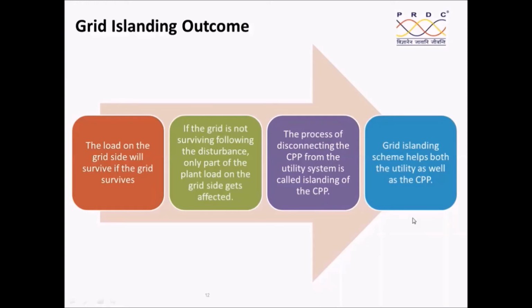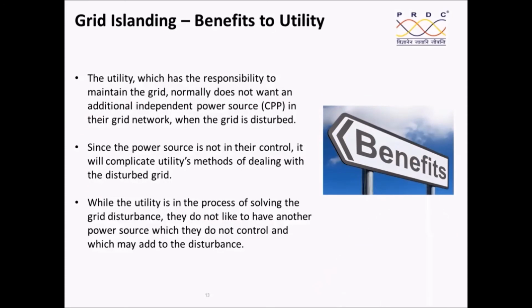Therefore, islanding helps both the utility as well as the captive power plant. This is what is important for us to understand: what are the benefits to the utility? Assume that a utility has the responsibility of maintaining the grid and there is a disturbance in the grid. They don't want the captive power plant to contribute to the grid disturbances. They would like to ensure that one more additional power plant, a captive power plant, is not interfering with the grid disturbance. Therefore, for the utility also, they would like to ensure that whenever there is a problem in the grid, the CPP gets isolated. Why? Because the power source is not under their control. They would like to ensure that the captive power plant gets isolated, and the utility is in the process of solving their problem. They don't want another power source on which they don't have any control. Therefore, they would like to ensure that there is a proper islanding scheme by which one can get islanded.